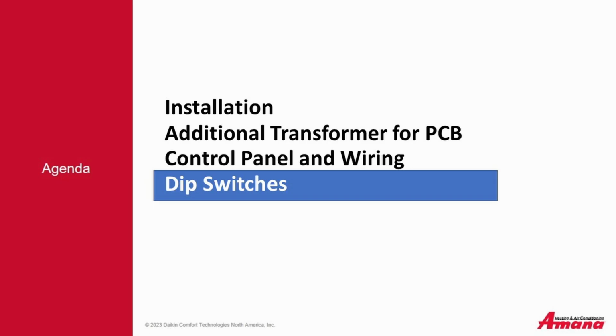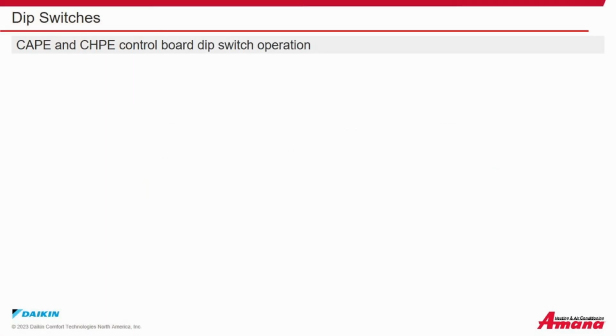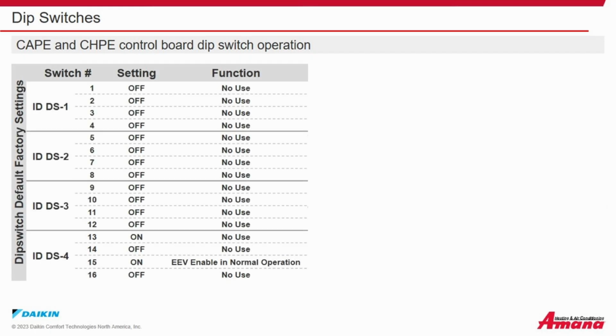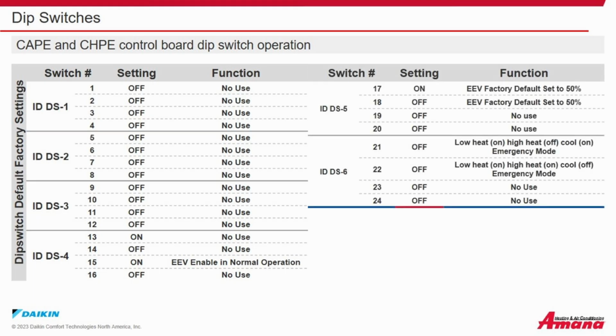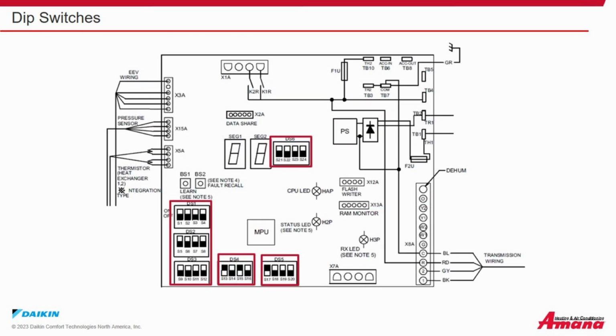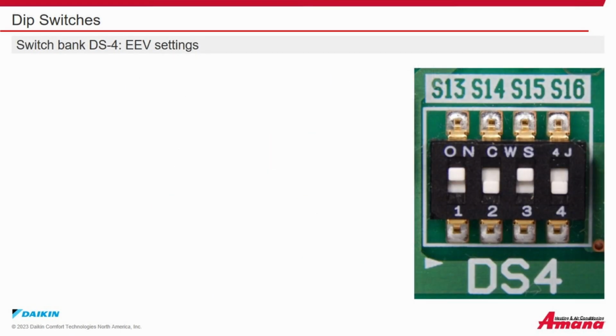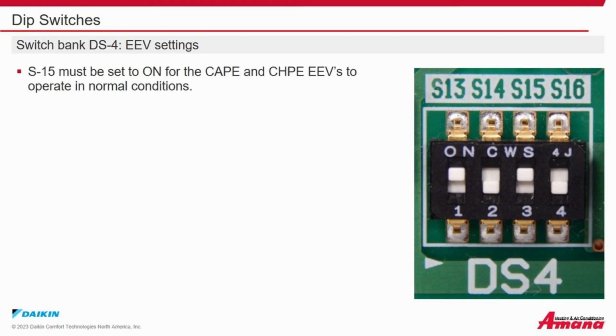Dip switches. The CAPE and CHPE control board dip switch operation. Here is a list of the factory default dip switch settings for dip switch 1, 2, 3, 4, 5, and 6. And here is the location of those dip switches on a circuit board. Switch bank dip switch 4 electronic expansion valve settings. S15 must be set to on for the CAPE and CHPE electronic expansion valves to operate in normal conditions. S16 is not used.